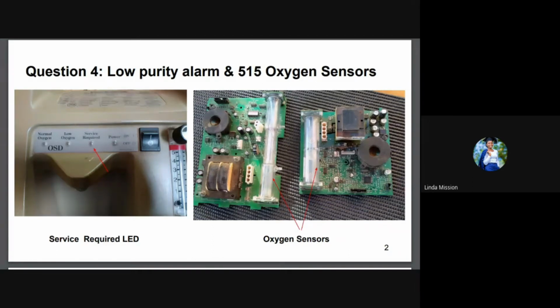So in the DeVilbiss 515, the oxygen sensor is usually soldered to the control board and might be hard to acquire separately. So you just need to change the whole control board whenever the oxygen sensor is faulty. As you can see in the graphics, those are the 2 oxygen sensors which are found on the control boards.